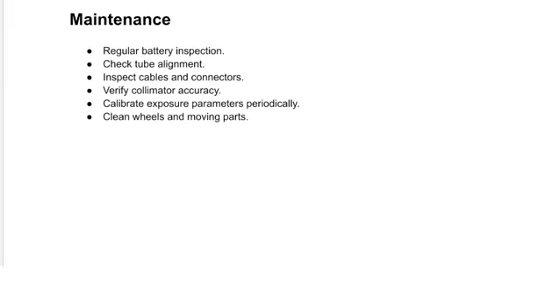And next is about the maintenance. Actually, a regular battery inspection is required, and we should check the tube alignment. We should inspect the cables and the connectors. We should verify the collimator accuracy. We should calibrate the exposure parameters periodically. We should clean the wheels and the moving parts, etc.